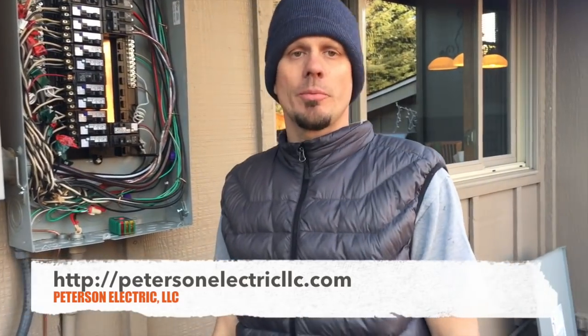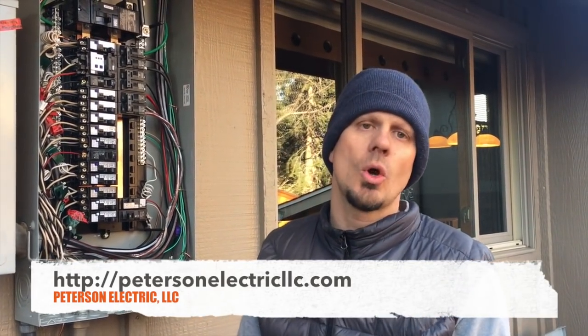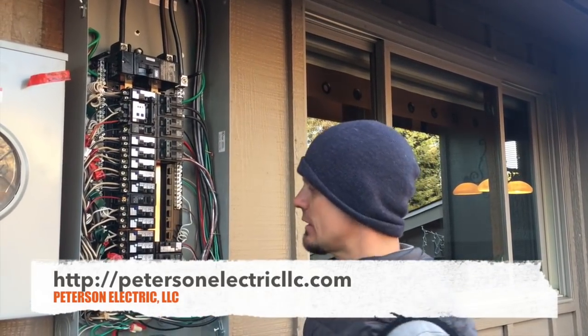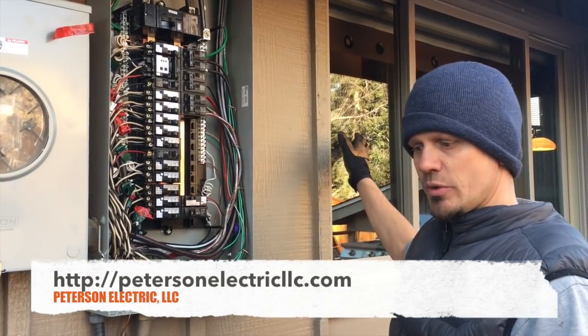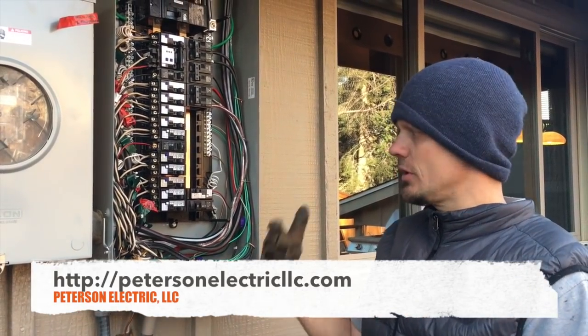Anyway guys, I've taken way too much time in this video but I hope that helps you out. This is at the end of 2014 — I'm changing in one week to the new 2017 code, which will be adopted by May, so we don't know yet if cities are going to start requesting all these arc fault breakers. I've heard they might. I know Westminster in Colorado is doing it — if your jurisdiction is enforcing it, feel free to send me an email on YouTube. In my opinion, start practicing it: if you are changing all your plugs and switches to update copper over aluminum, you should arc fault — that's what the code states. If you start tripping, hopefully there'll be some other videos to help you trace that inside the house. Thanks again guys, we'll see you next week.